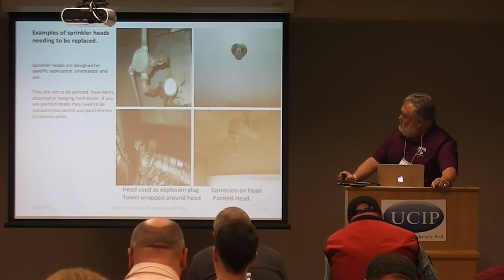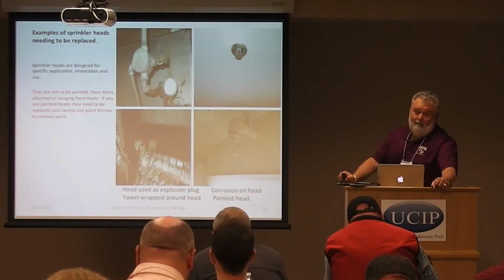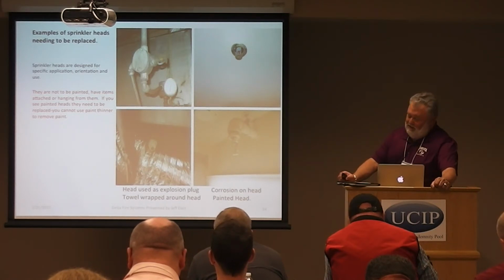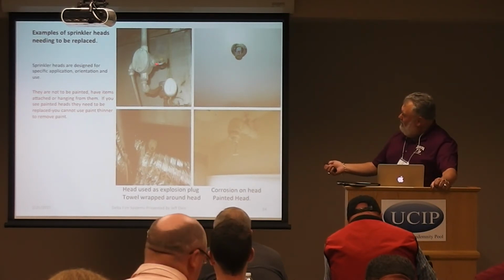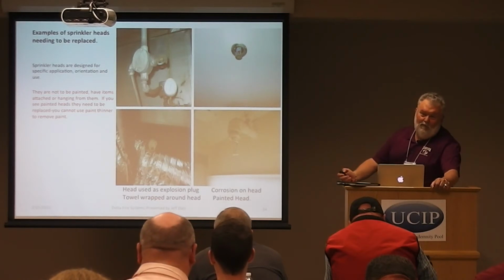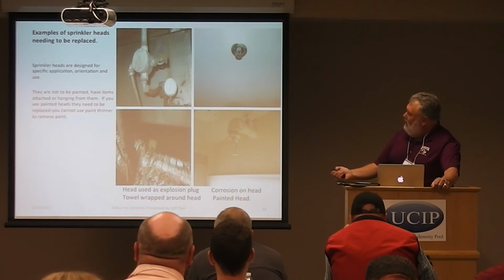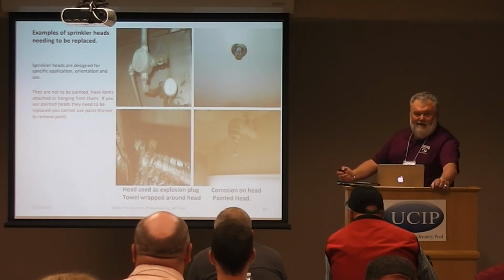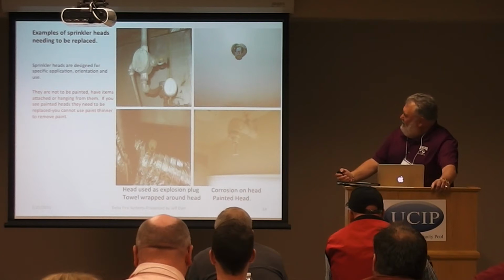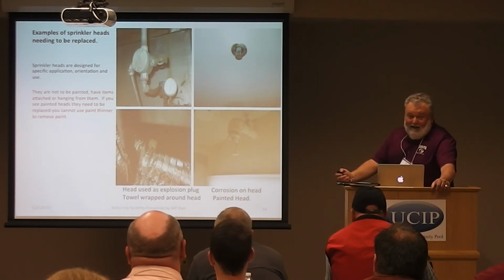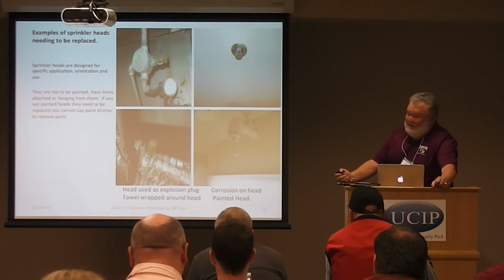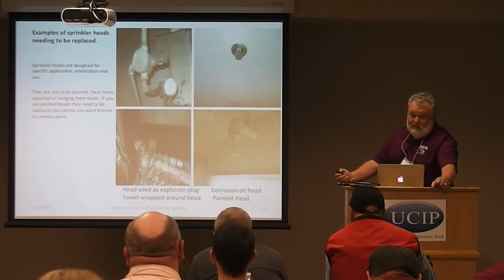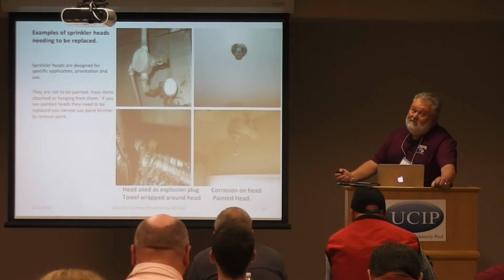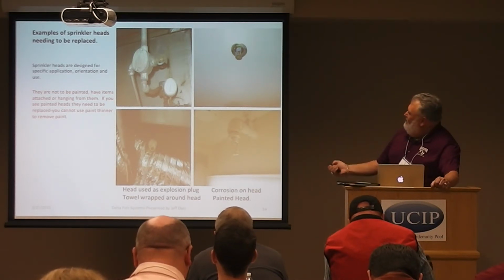I wanted to show you some examples of sprinkler heads and their improper use, or these heads need to be replaced. This one up here, for the life of me, I can't figure why they used the sprinkler head as an explosion-proof plug on an electrical device. I guess the maintenance guy was pretty ingenious on that, but that definitely doesn't meet the intent of what the sprinkler's intended for, and it doesn't meet the electrical code, either one.